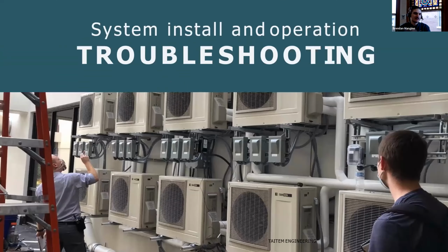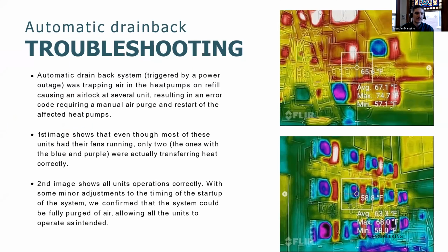So, system install and operating troubleshooting. That was the design challenges we ran into when designing the system, but we also ran into a couple of issues during install and operation. The first was this automatic drain back system. The automatic drain back system worked great in getting the water out of the heat pumps.